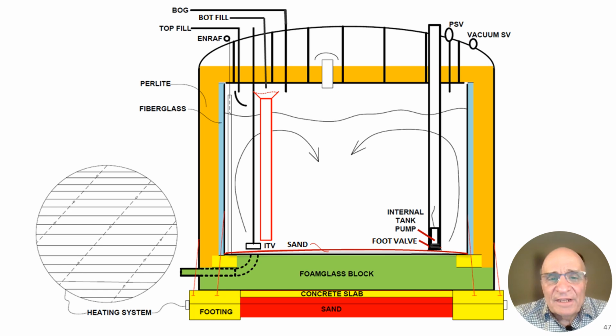Now, this is very common, and only in recent years have they realized that this can become problematic. Because let's say you're filling a very light LNG into the tank. Where do you want to put a light LNG? You want to put it on the bottom. This way it mixes with the heavy LNG that's higher up. So if you have a light LNG, you want to put it on the bottom. But let's say it's very light LNG.